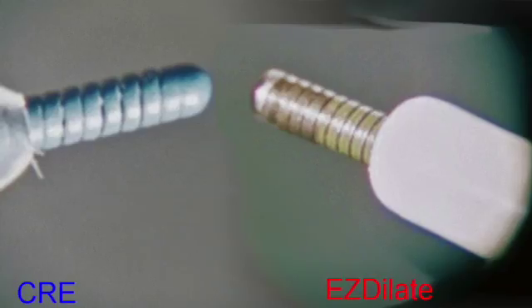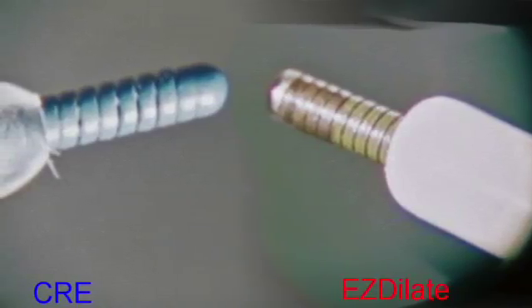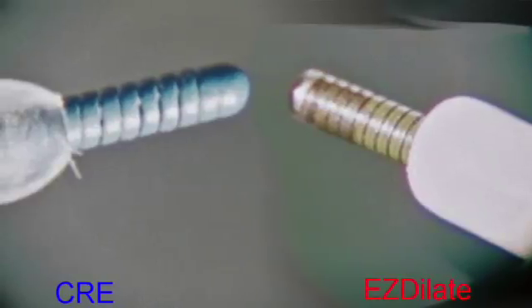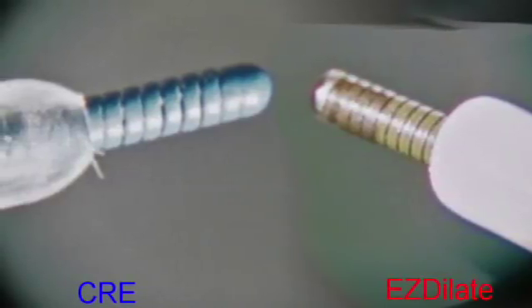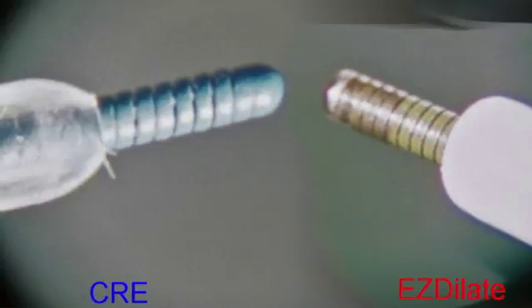At the other end, under the microscope, you can see that the tip of the dilators are nicely rounded with both of them. Surprisingly, perhaps, I measured that when you feed these dilators down the biopsy channel of a 2.5 millimeter diagnostic endoscope, you would have predicted that the Olympus balloon would be exerting less drag. But it doesn't. It exerts more drag. I measured the drag at 6 newtons with the Olympus balloon, which is thinner. It makes no sense compared to the CRE balloon, which exerts a resistance, a drag of 2 newtons.